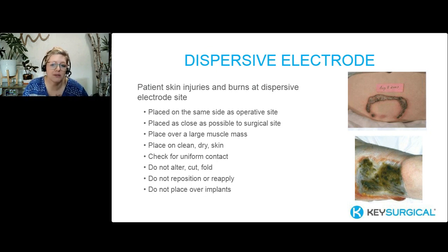And then, not placing over metal implants. Again, remembering this is electrical current applied to a patient's body. It will follow any and every path that it can to escape, to get out, to keep going. So if we place this over a metal implant, we're really just begging for that electrical current to go through, cause a burn, heat up that metal device inside the body, and then escape through the dispersive electrode.